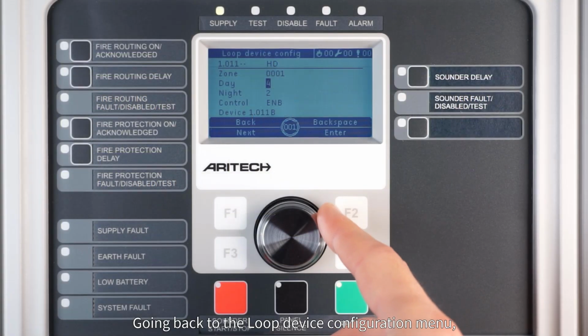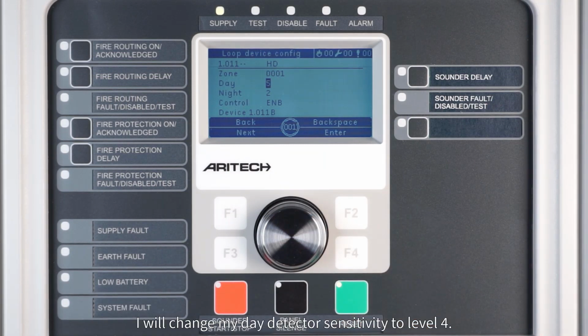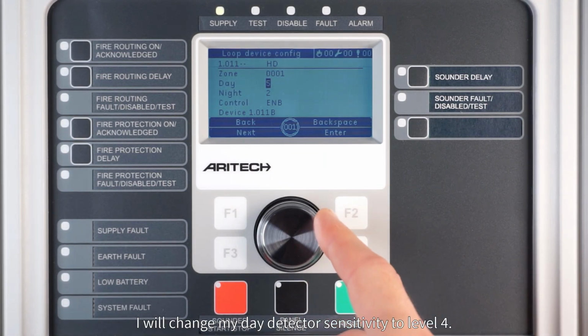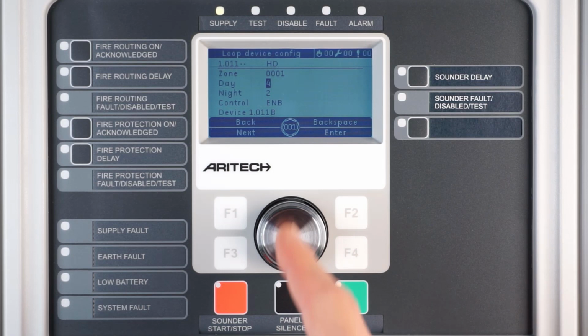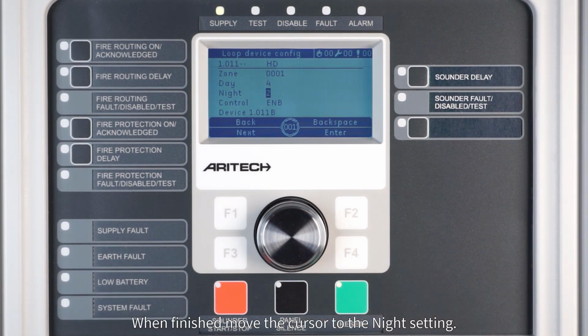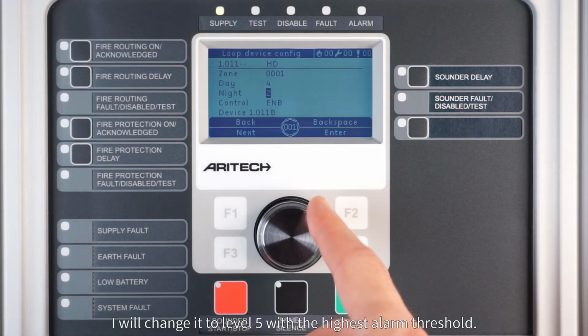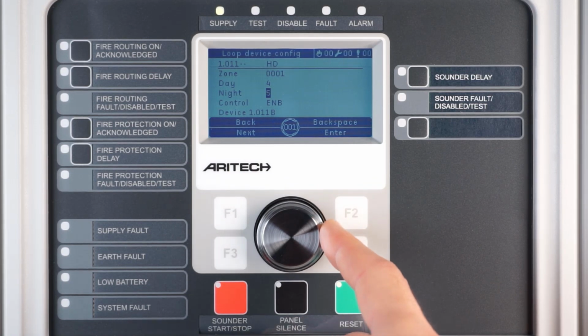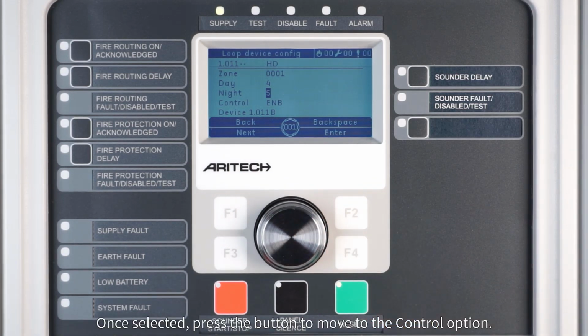Going back to the loop device configuration menu, I will change my day detector sensitivity to level 4. When finished, move the cursor to the night setting. Now you can select your nighttime operation sensitivity. I will change it to level 5, with the highest alarm threshold. Once selected, press the button to move to the control option.